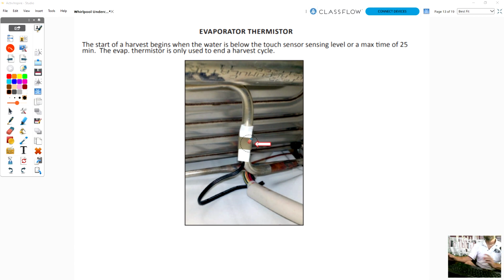So you have to know if you're doing the newer or the older model. And I guess the only way to know is if it has a water level sensor, that's what controls it. And you're going to have to find that on the diagram. So on the older ones, this thermistor went bad a lot, and we had poor ice, or sometimes you would get improper ice thickness because the sensor's not functioning properly.